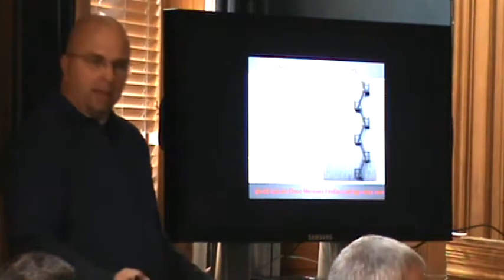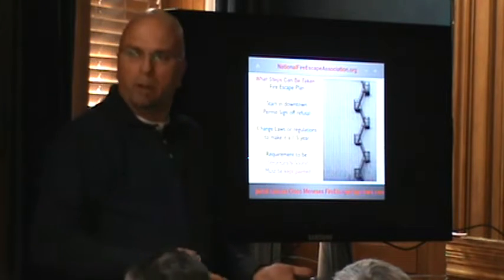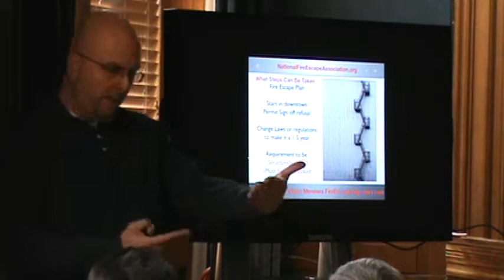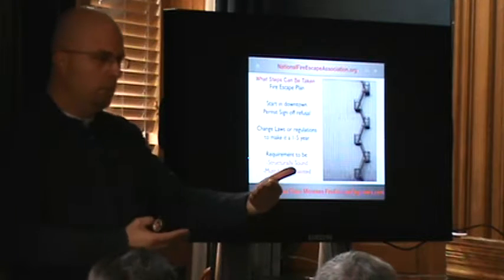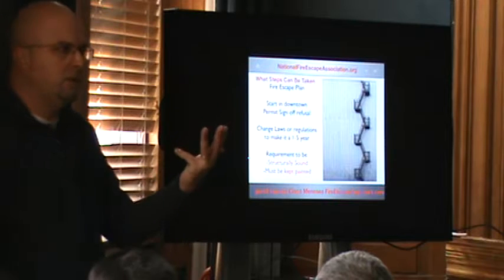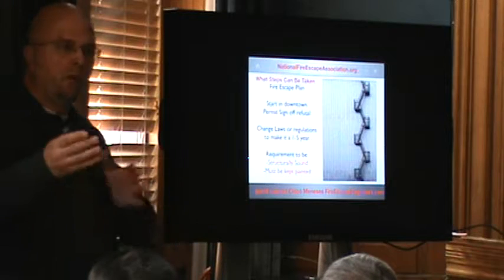He goes, photograph, photograph, photograph. That's it. That is what gets submitted to the city official. And they sit down at a desk and say, hey, these are all the things that I found. Vendor XYZ is going to come in here, pull a permit, and he's going to fix these things, because the client has chosen to spot repair everything I've identified here. And then we're going to proceed to a load test. Or, here are some photographs, and basically we're going to change every bolt out. And I've already got three scheduled visits that I'm being paid for to basically watch this vendor change all these bolts to avoid the load test.